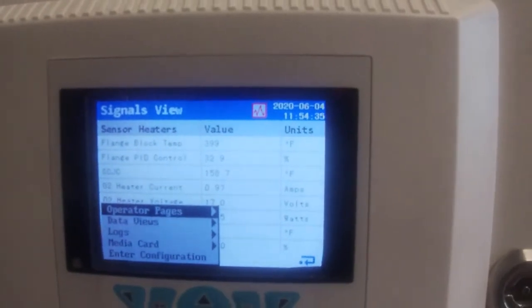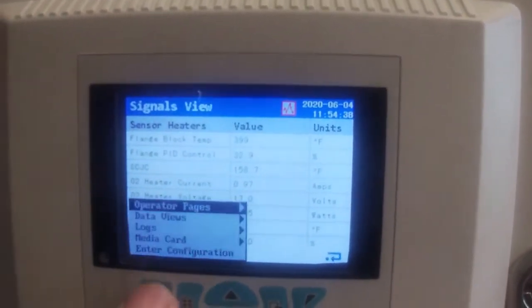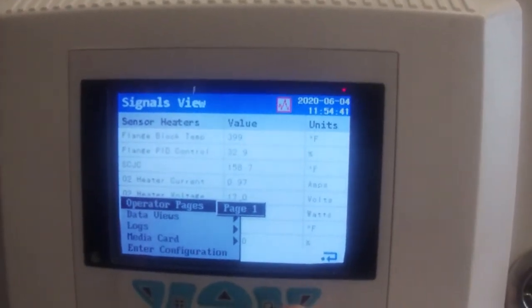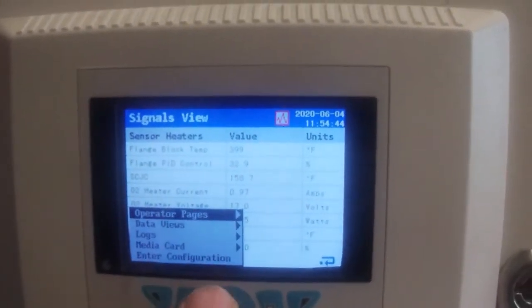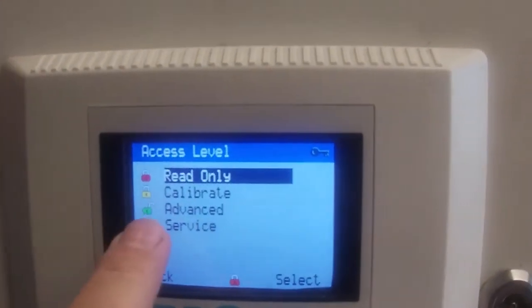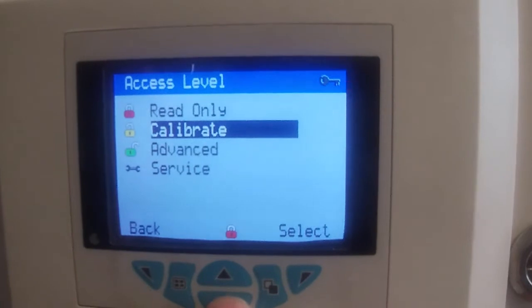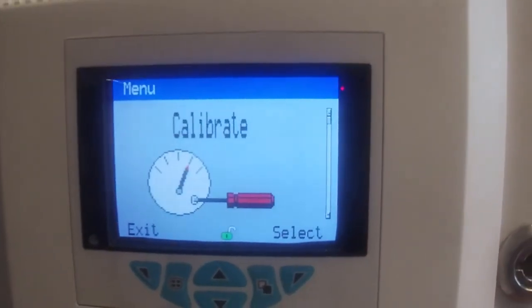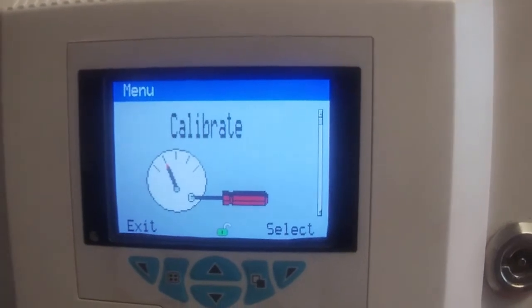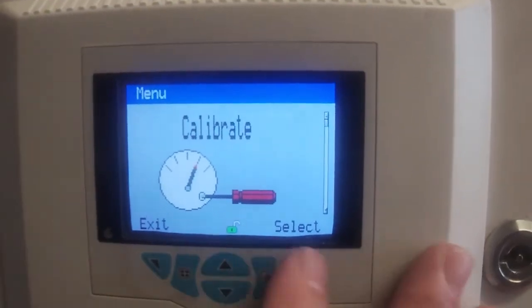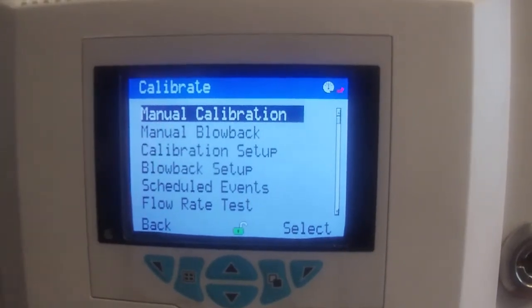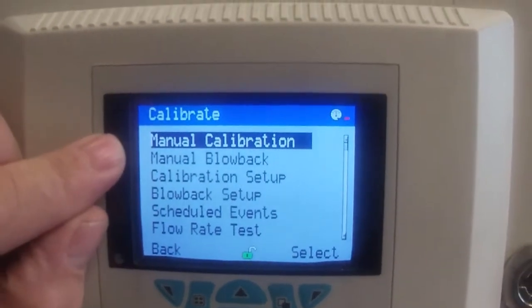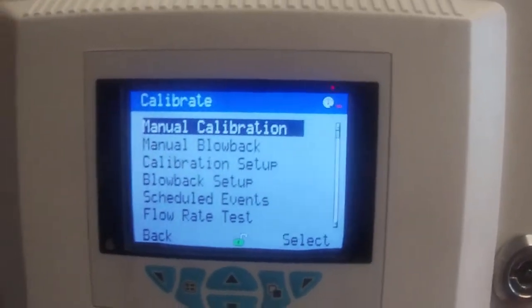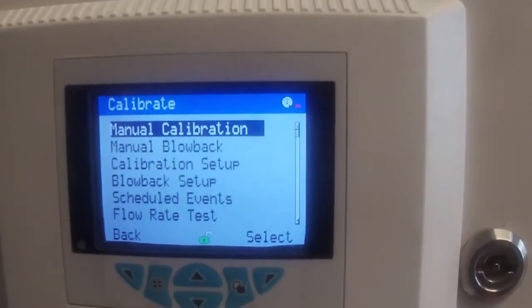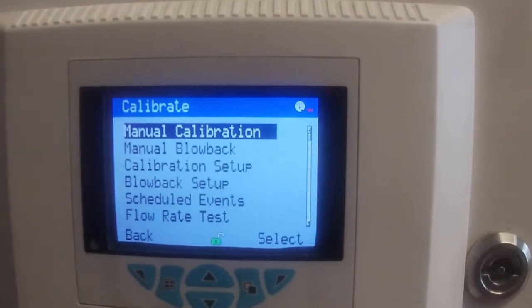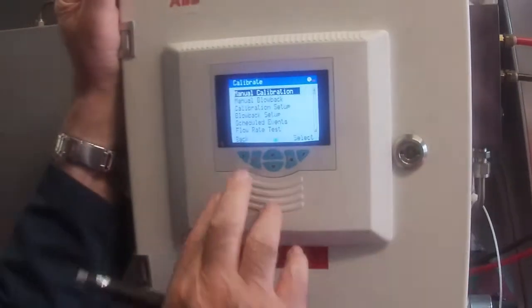Now, I want to calibrate this thing, and so going into calibration, I set it up to go through the configuration page, and I set it up so we would come in under advanced, and we'll go to select, and what it'll let you do is go to calibrate. But we got some things we have to do in advance for the calibration. So if I hit the select, these are the things I can do. I can do a manual calibration. I can do a manual blowback. What they've set this up for is that you can actually take air and purge it backwards to actually clear the unit out, if in fact it's got some blockages inside.